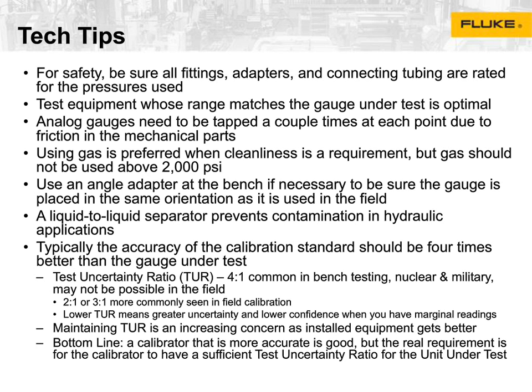Frequently, we'll see guys out in the field calibrating at 2 to 1 or 3 to 1, and sometimes they can't even get that. And at that point, you have to start to wonder, is it really worth doing the calibration? And so people will say, well, we can't calibrate it if we're at 2 to 1. Well, that's not entirely true.